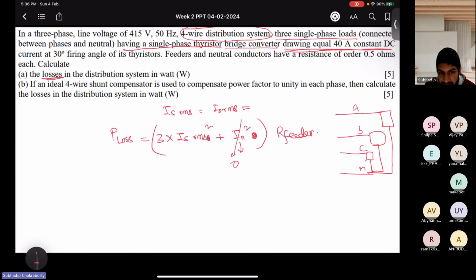So I_N goes away, and then you have I_S RMS. I_S RMS we know is I naught RMS, which is given as 40 amperes. So 3 into 40 square into R feeder. R feeder is 0.5 ohms. Neutral, there is no current, so no loss for the neutral feeder because current is 0. So what is the power loss? Can anyone tell? 2,400. Okay.